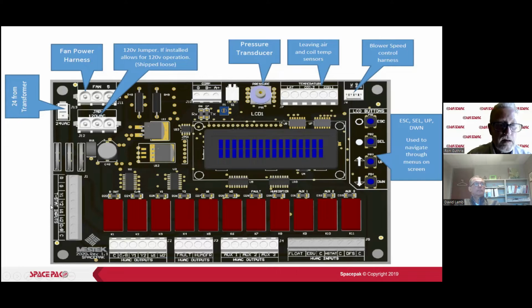Okay. Now, to get around the board not wanting to allow Y1 or Y2 at the same time as W1, basically, you're going to take from this bottom level, I'm trying to get my pointer working here, you're going to take Y1 and you're going to move it up here to the thermostat contacts. So what that does is it bypasses the board for Y1. And this goes from the thermostat directly to the outdoor unit and says, hey, bring on Y1. But what it does, though, when we do that, is it also bypasses the freezestat capability in the board for when we go back into cooling mode. Okay, so this is a temporary fix.